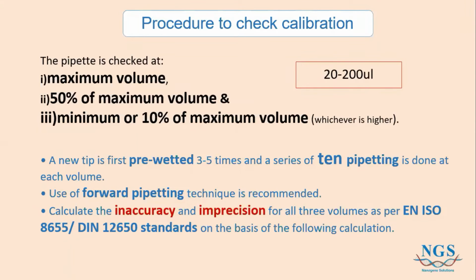All right. So now we know that we have 3 checking volumes to look at. So how do we go about that? So with each of the 3 checking volumes, you want to do 10 series of pipetting. So for example, you would set your volume to the maximum volume, which is 200 microliter, aspirate your liquid, and then dispense your liquid onto a weighing machine, and then you want to read the readings. So you do that 10 times. So for each volume, you will have 10 readings. Forward pipetting technique is recommended in this test. And at the end, you'll be calculating inaccuracy and imprecision for these 3 volumes. All right.